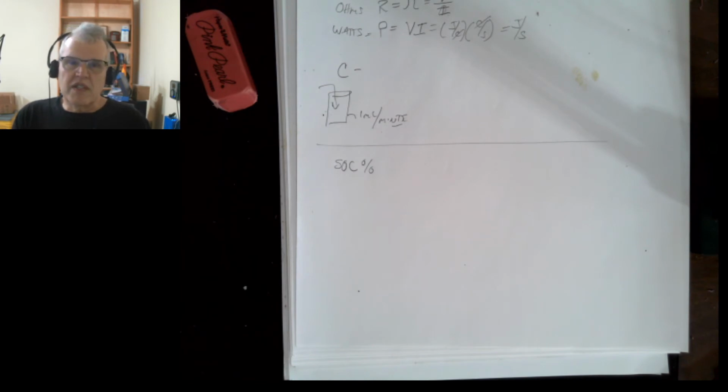Even though internal resistance is really what's going on, almost never do we do anything by internal resistance. It's almost always done by impedance. What is impedance? Well, impedance is usually for AC, more for AC, not for DC. And it just includes the reactance and the capacitance, and I can't get into all that stuff. But we use impedance rather than resistance because impedance is much, much easier to measure than resistance is. Resistance is a little bit complicated. It's not that complicated, but it is a little bit complicated. And it's going to be voltage, it's going to be state of charge dependent, and things that we don't like.